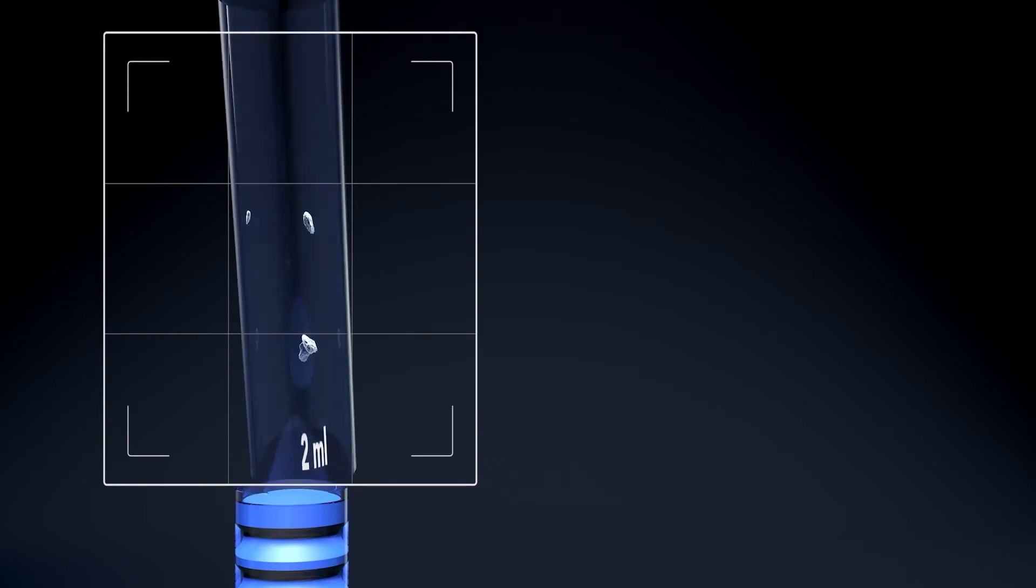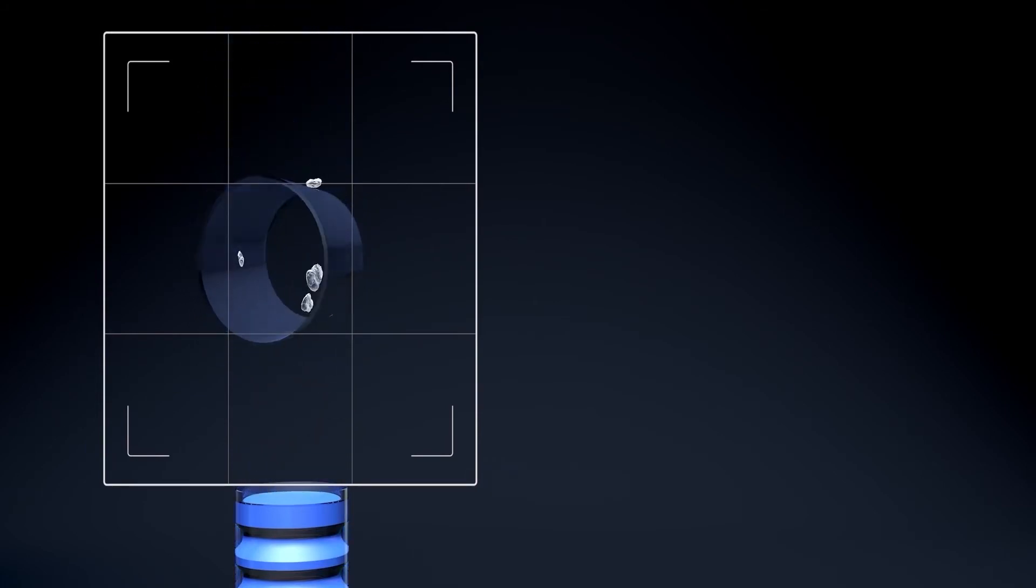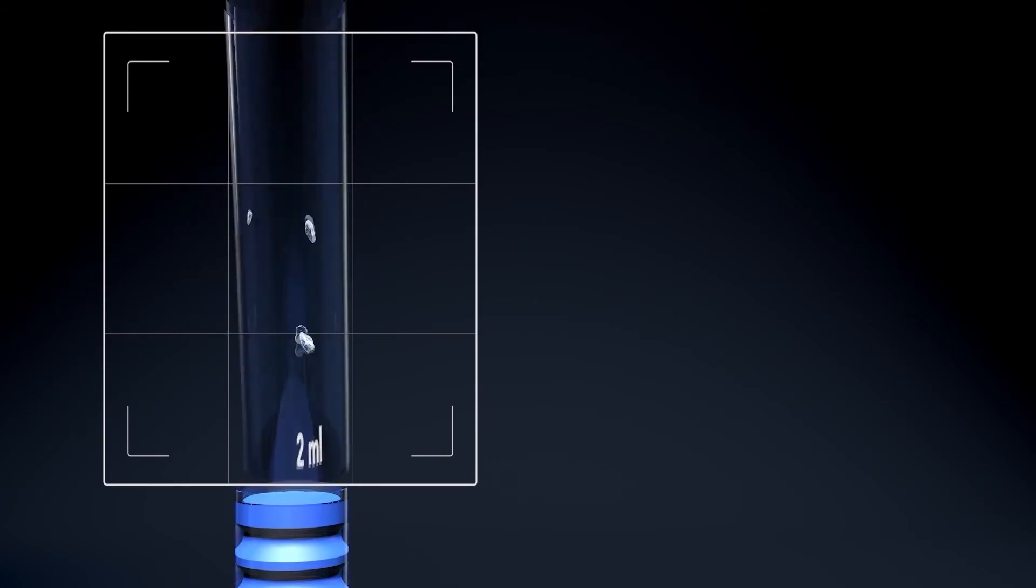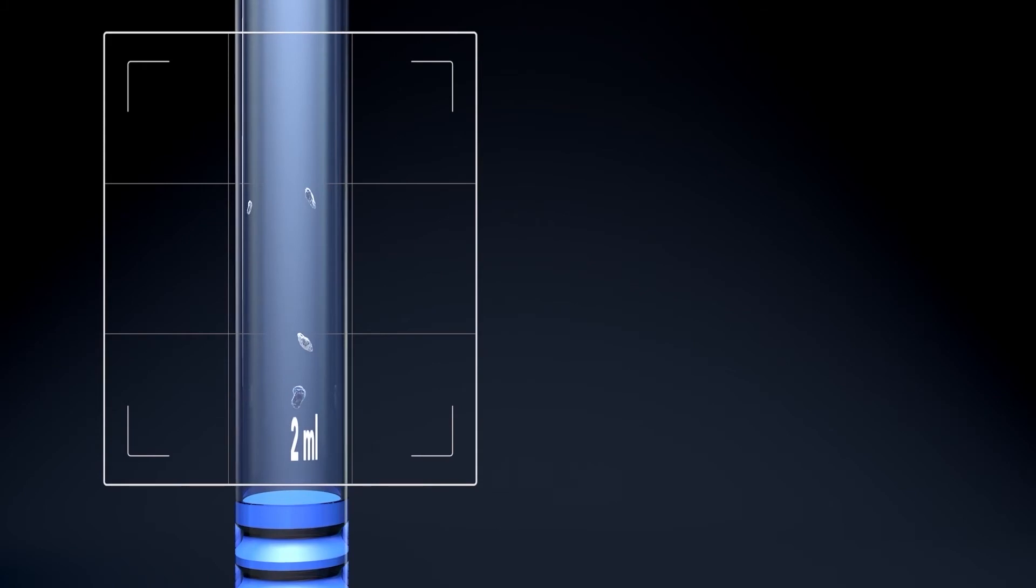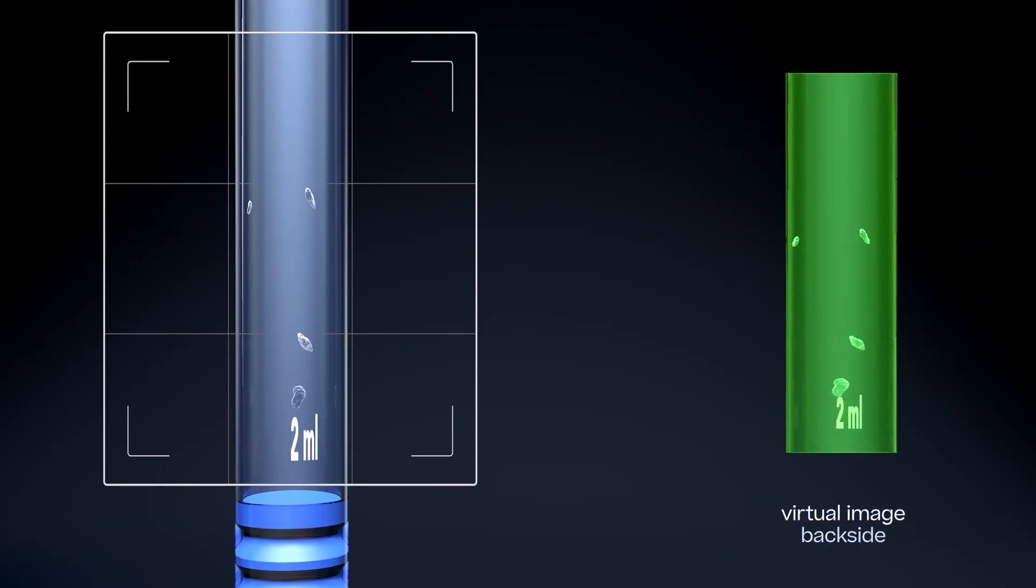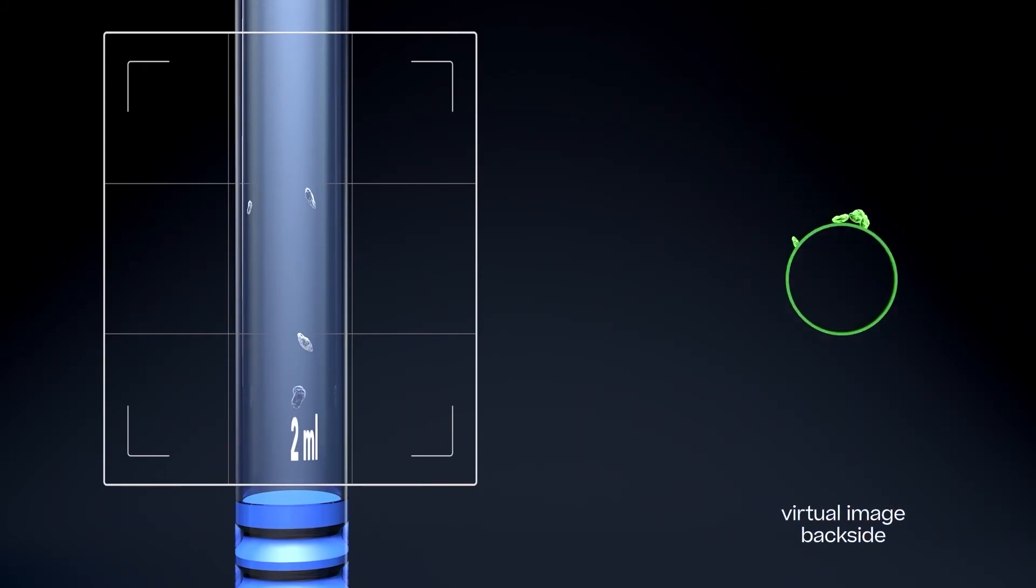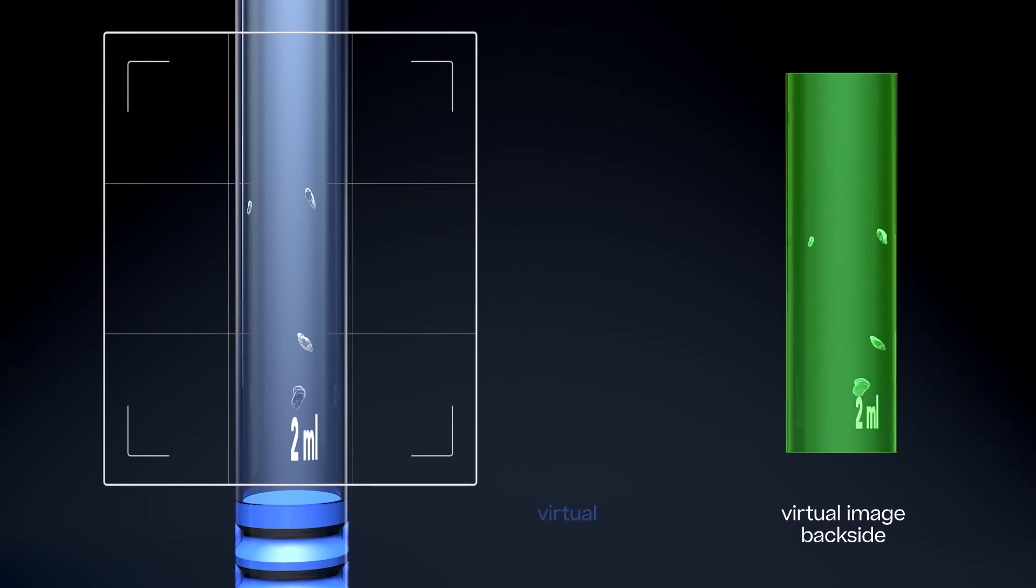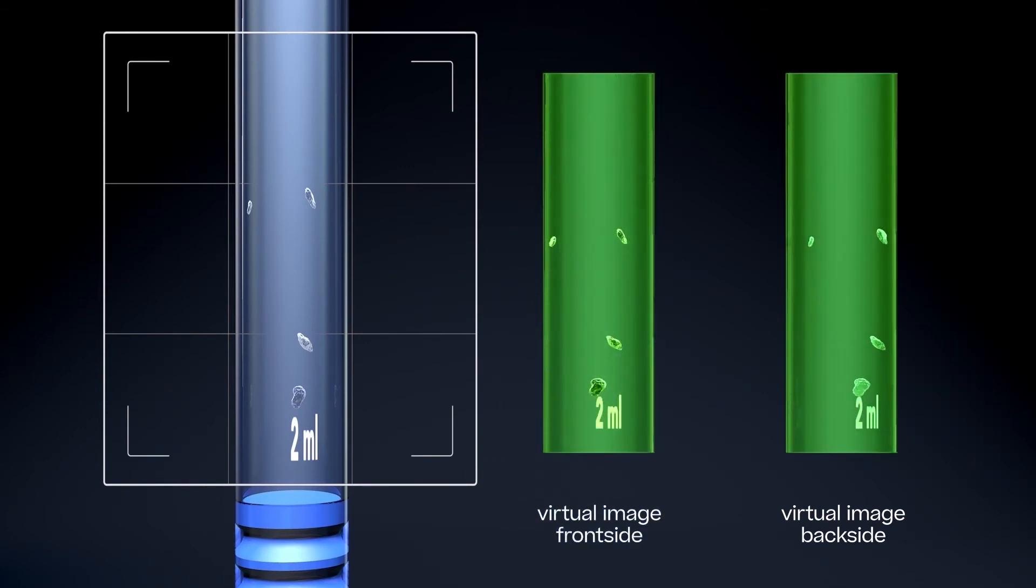In the first stage of 3D inspection, the camera takes an image. To distinguish between particles inside and outside the container, two virtual images are being generated. It is initially assumed that all particles which are visible on the real image are located outside and on the back surface of the container. A calculation is now carried out to see how the image would look like after rotating the container by a defined angle.